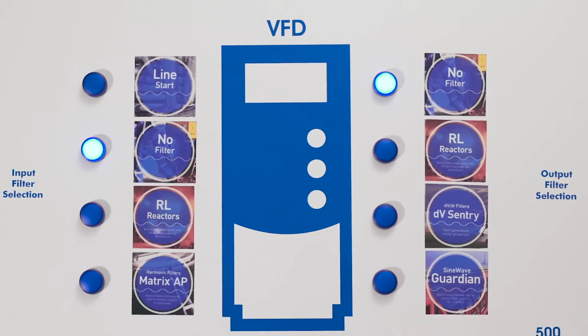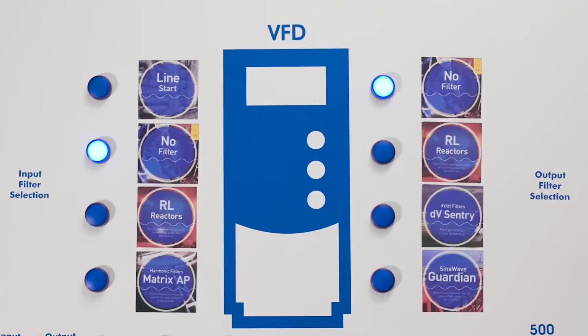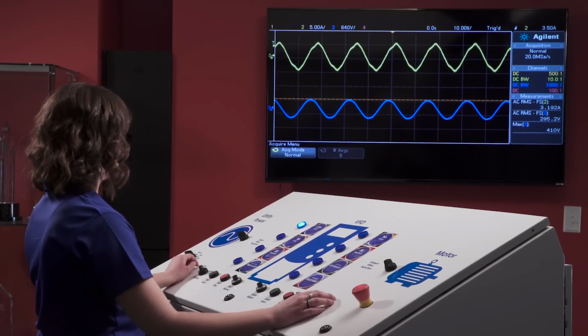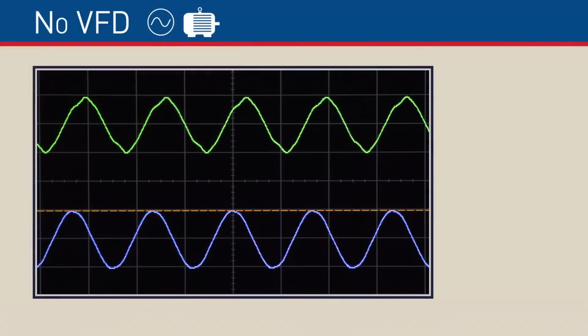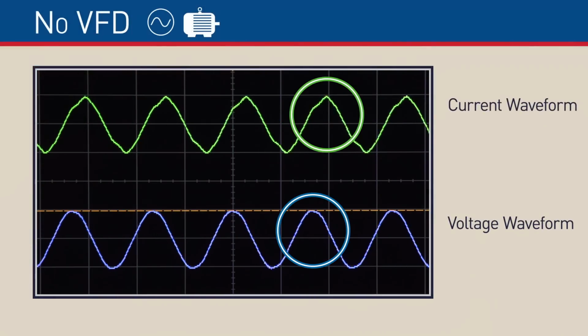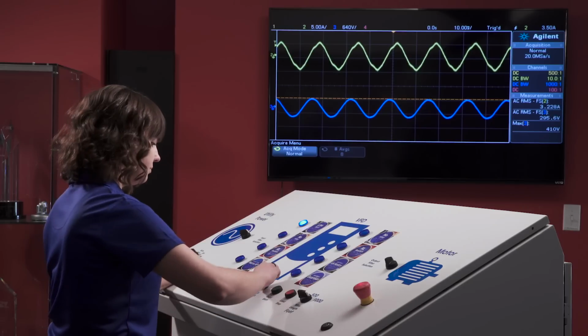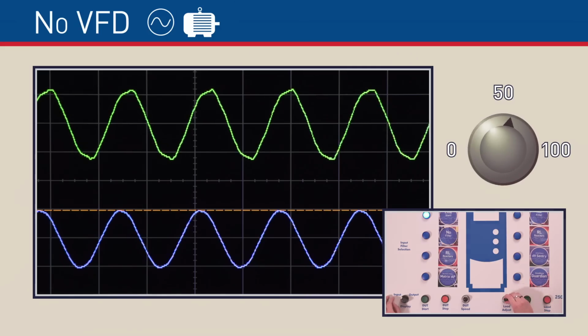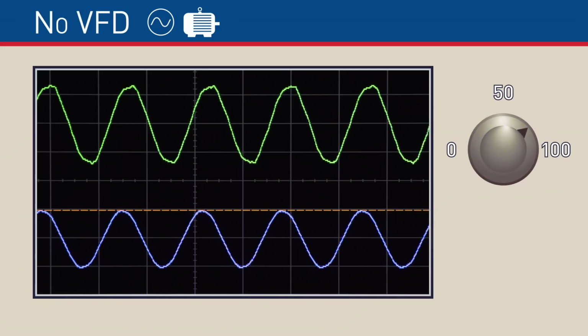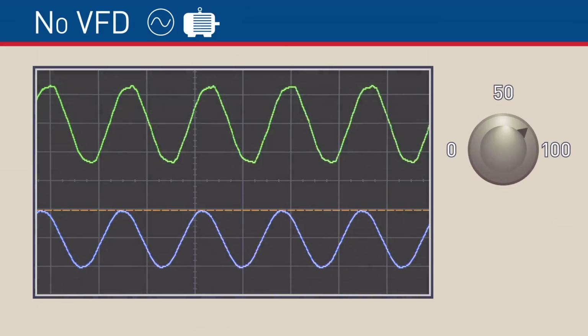First, we'll run the system with power going directly to the motor so that we can see what the current and voltage waveforms look like. The voltage waveform is on the bottom in blue, and the current waveform is on the top in green. As we increase the load, the well-defined sinusoidal waveforms indicate that we have good power quality in both. But there are several downfalls to this type of application, mainly a lack of efficiency.